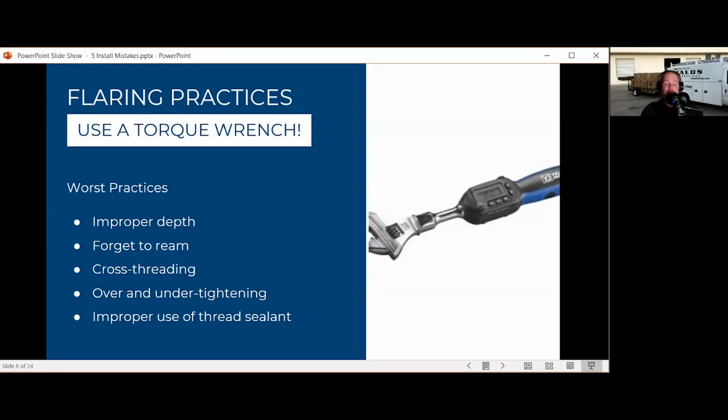Now, one thing to mention there is that will change your torque spec. So what I say is most manufacturers will give you a torque spec range. I would not go to the tighter range. I would stay on the looser side because you can easily over tighten when you use an assembly lubricant like Nylog. And that is a feel thing because the spec's not going to tell you. And that's actually one argument that people will use for not using it.